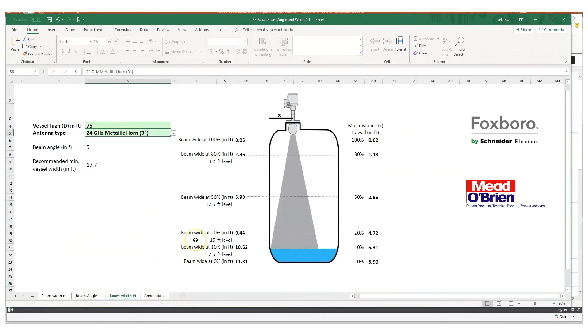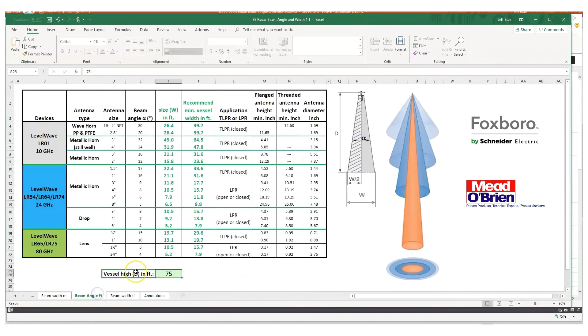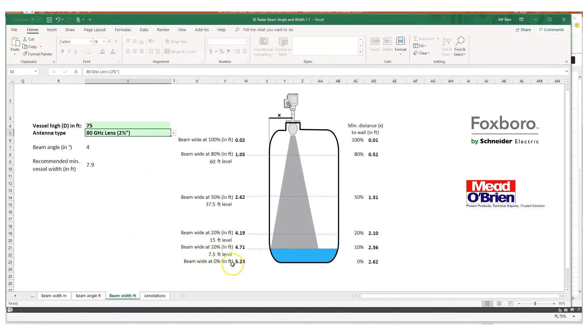So back to the, if you remember the nozzle and the valve we looked at, we could actually figure out if we plugged in 75 feet and we wanted to go with the most narrow beam we could find, that would be an 80 gigahertz with the two and three quarter inch lens. We've got our four degree beam angle. So it's 75 feet all the way at the bottom of the tank. If you remember, if we had 5.2 here, we could see 5.2 feet. That's how big that beam is going to be at the bottom of the tank. At 50 percent high, it's going to be 2.62 feet. At 80 percent high, it's going to be just a little over a foot.